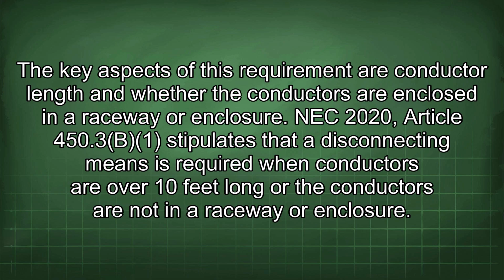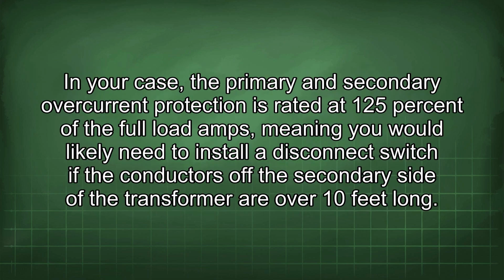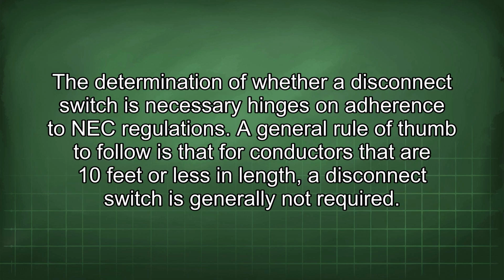NEC 2020 Article 450.3(B) stipulates that a disconnecting means is required when conductors are over 10 feet long or the conductors are not in a raceway or enclosure. In your case, the primary and secondary overcurrent protection is rated at 125% of the full load amps, meaning you will likely need to install a disconnect switch if the conductors off the secondary side of the transformer are over 10 feet long. The determination of whether a disconnect switch is necessary hinges on adherence to NEC regulations.